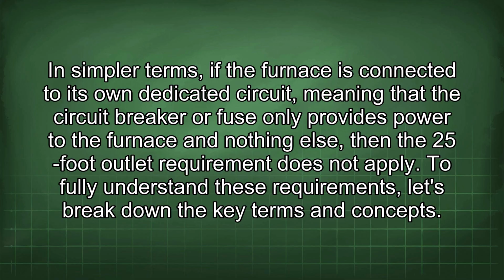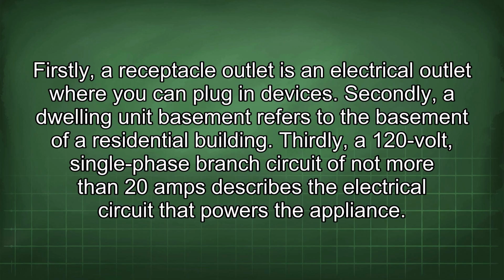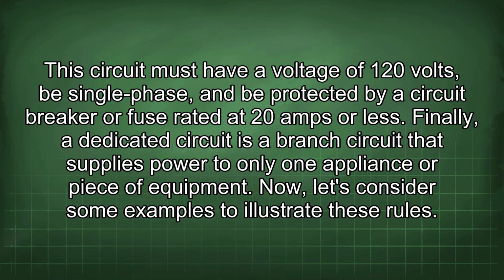To fully understand these requirements, let's break down the key terms and concepts. Firstly, a receptacle outlet is an electrical outlet where you can plug in devices. Secondly, a dwelling unit basement refers to the basement of a residential building. Thirdly, a 120-volt single-phase branch circuit of not more than 20 amps describes the electrical circuit that powers the appliance. This circuit must have a voltage of 120 volts, be single-phase, and be protected by a circuit breaker or fuse rated at 20 amps or less. Finally, a dedicated circuit is a branch circuit that supplies power to only one appliance or piece of equipment.